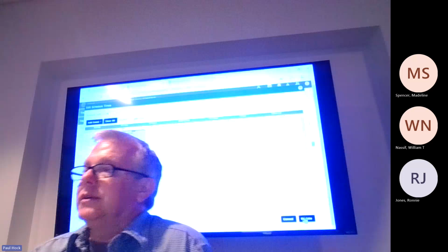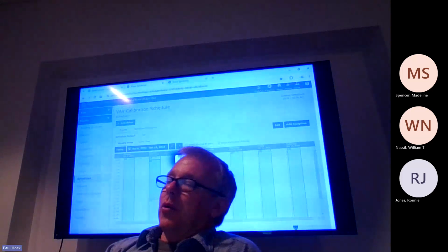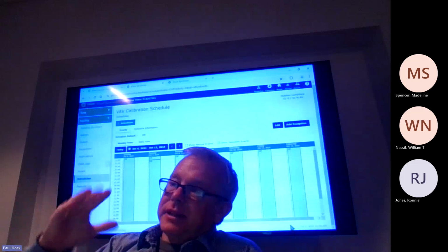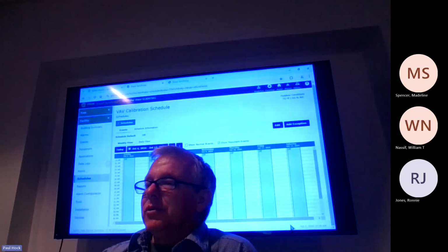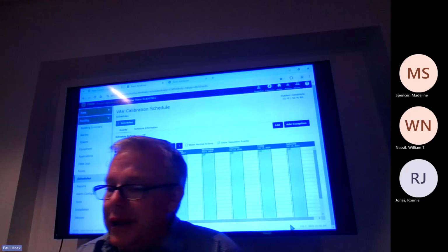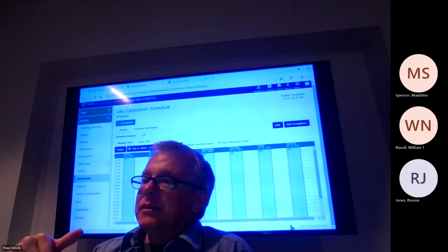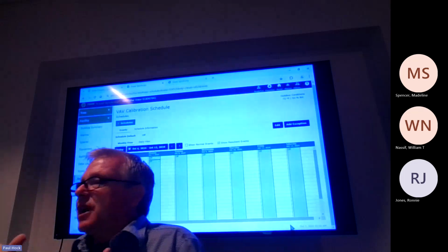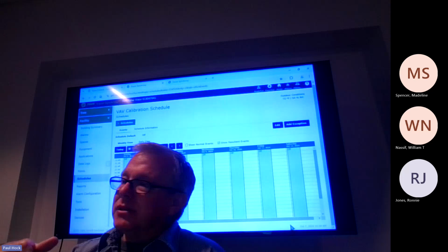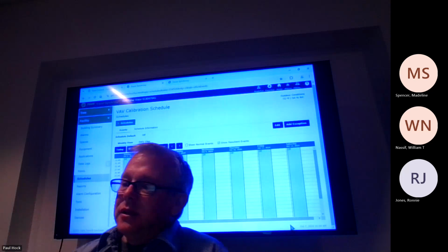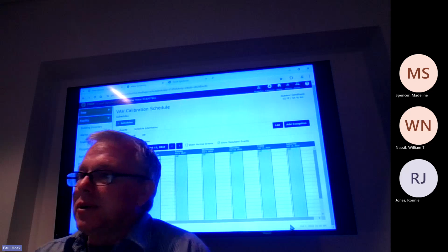So every Monday, after a while, the VAVs, the air dampers, they tend to lose track of the airflow. So what I do is every Monday at like 1 a.m., I have it going through and recalibrating them. But it's only going to do maybe like 6 at a time. It just closes them so they know where 0 is, and then they reopen up. So it only takes like 5 minutes for the signal to go to do it.